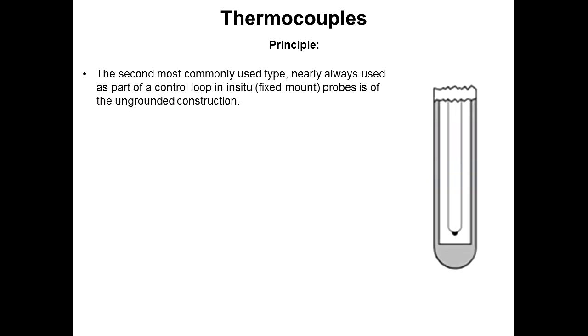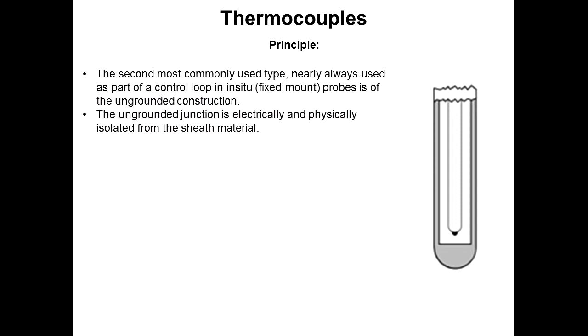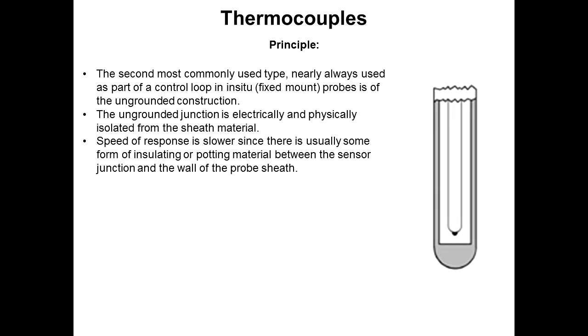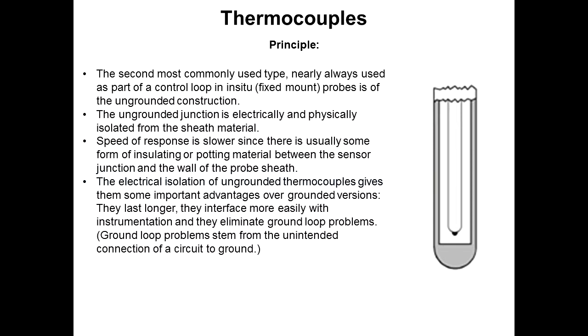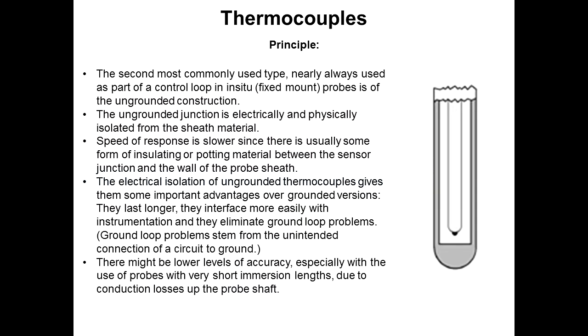The most common type for controls is an isolated or ungrounded one, where the thermocouple element itself does not touch the metal sheath. It's electrically and physically isolated. It's a little bit slower, but you can't have it grounding out your control loop. Also, they will last longer because they're subject to less direct vibration, which could break the welds where they're welded to the inside of the sheath, and the powder around them will protect them from vibration. And there's some lower level of accuracy for very small diameter probes and short probe lengths because of heat transfer up the probe.